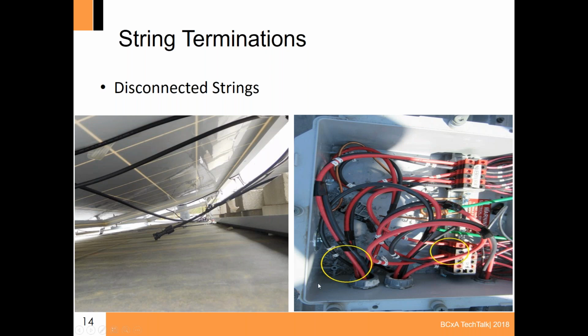And in this photo on the right-hand side, really tough to see, but you can tell this is a solar junction box or a pass-through box. What we're showing here, again, a little difficult to see, is that one of the black wires coming in from this conduit on the right loops around and then dead ends right over here instead of plugging into this terminal right here. So again, very difficult to see in the field, but this could be a result of troubleshooting when we get an outlier for that voltage test that I had mentioned. So that's one of the things that we would look for.